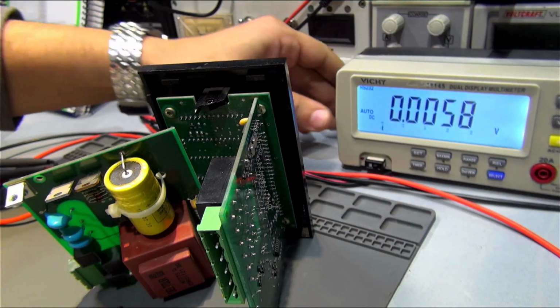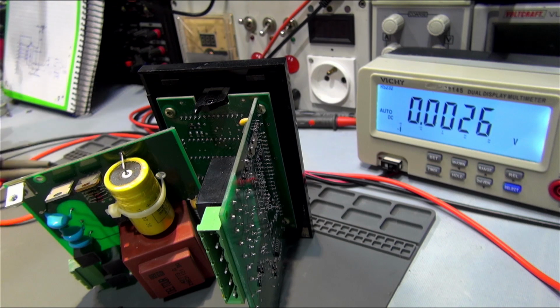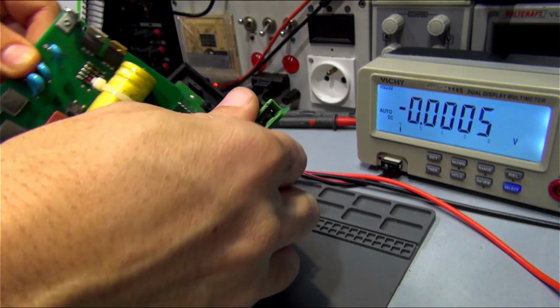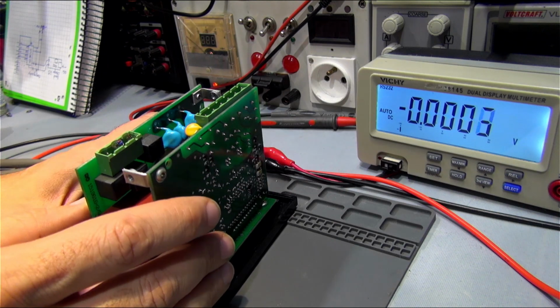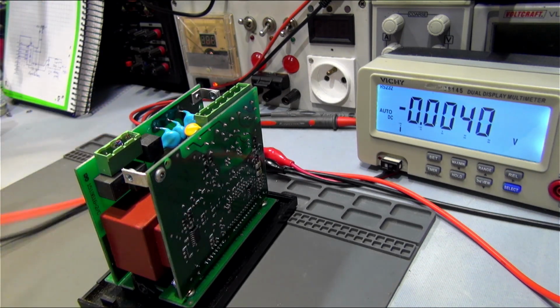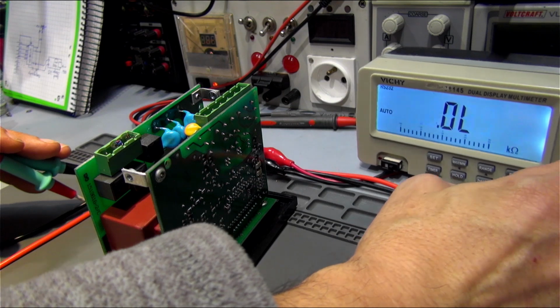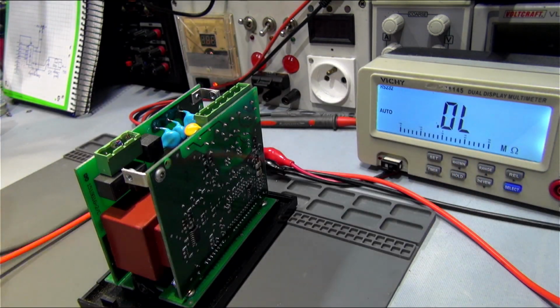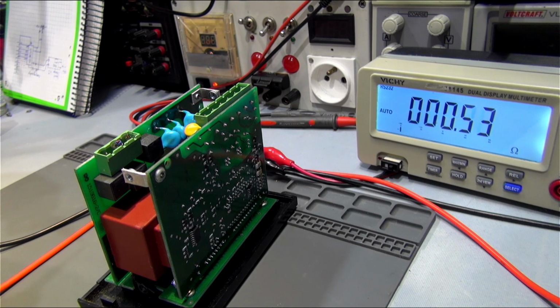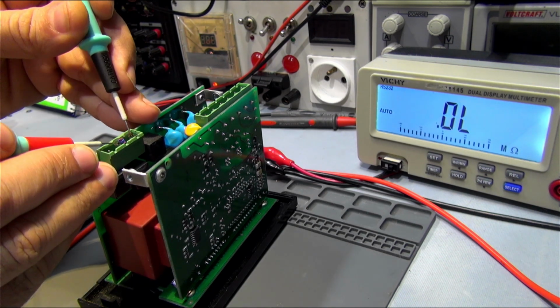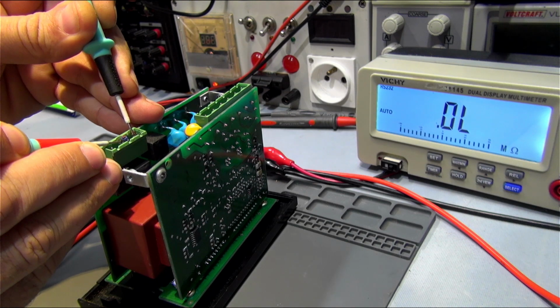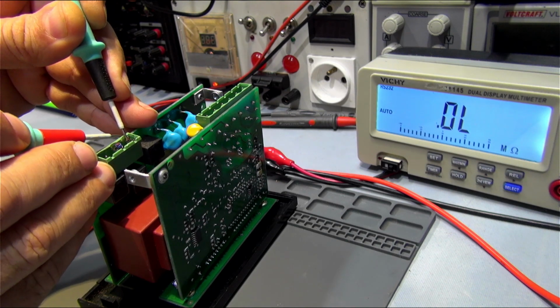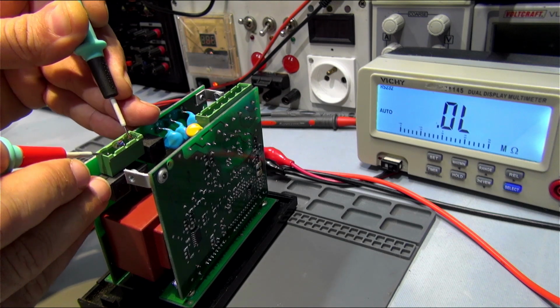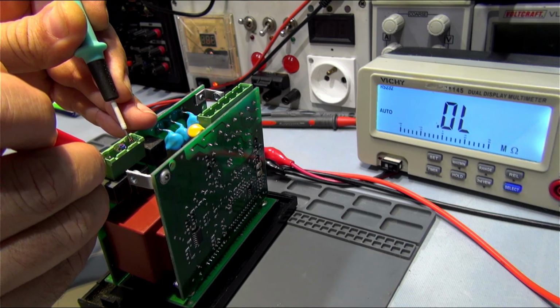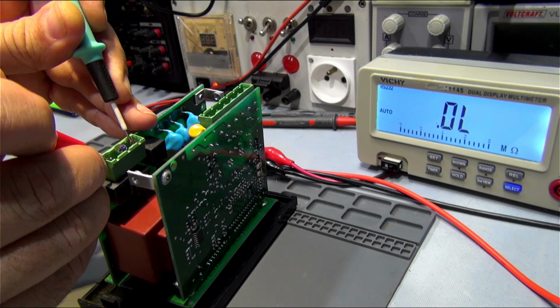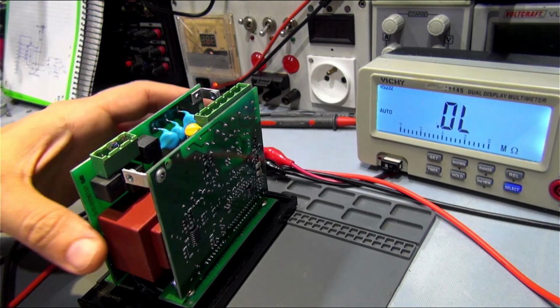So here we have the entry, and on the ohmmeter it will display something. You can see there is no current through the primary of the transformer. This is the 220 voltage side, and if I test it, there is no continuity. This transformer is probably dead.